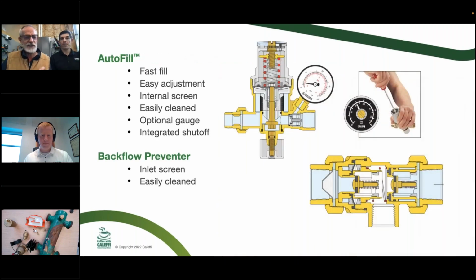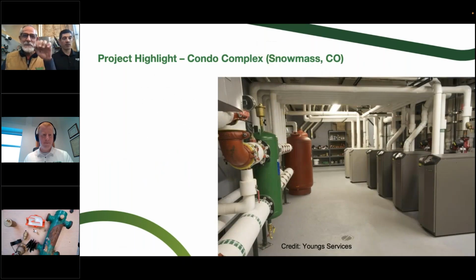I know it was just this job or one of the other ones. There was actually a condo project somewhere there in Colorado where they drilled a hole through the side, and they put little 1/4-inch copper tube off the bleeder elbows on all the baseboards, and they would just pee it outside every time. Well, I'm not going to take a sponge up there every time, I'll just open it up and blow it out the side of the building. So imagine the property managers rejoiced when they didn't have to do that anymore. Or somebody walking by that building when he's opening up, and water is peeing out the side of the building. So it was a good fix to something that had to be purged all the time, but the best case scenario is we just prevent that from being a daily task.